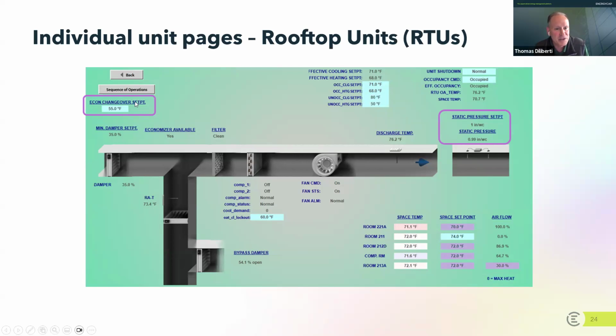They have an economizer changeover set point. So an economizer, I mentioned this in our webinar the last time, is a damper control strategy to suck in more outside air when the outside air is good. It's the right temperature, it's the right humidity level, and you want to get free cooling from outside and not have to manufacture cooling. So this economizer set point is the temperature when the dampers are going to start to take control. So they will open or close depending upon what the conditions are outside.